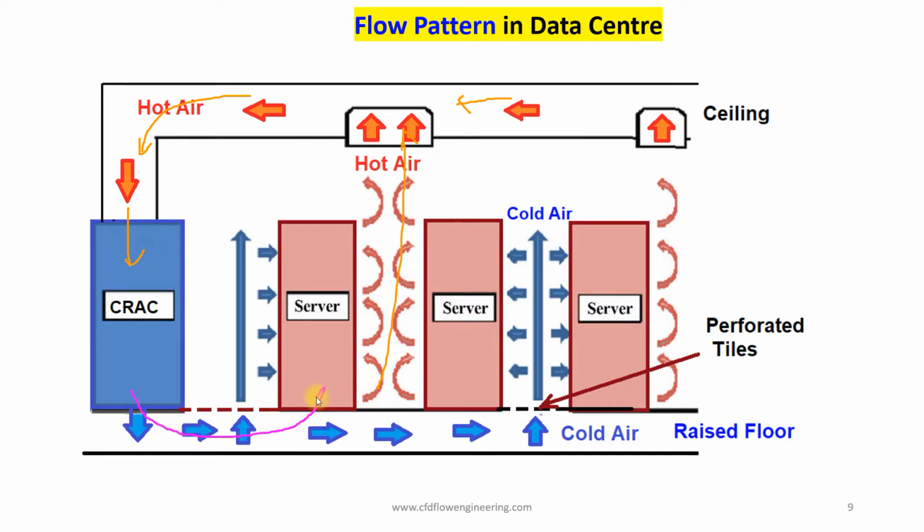Then cold air passes again through the bottom perforated plate. Because of this raised floor, the cooling will be more effective. For a small data center, a raised floor is not required. You can blow air from the bottom side to cool the server.